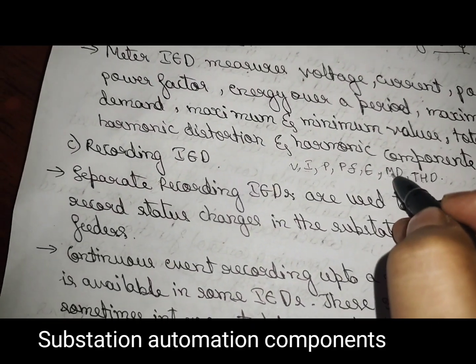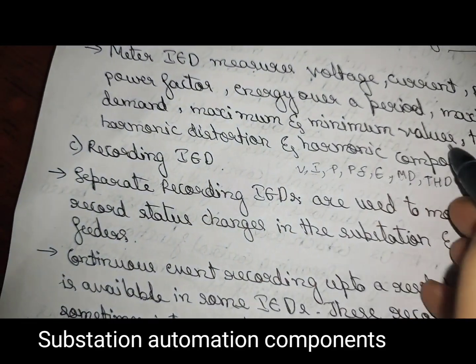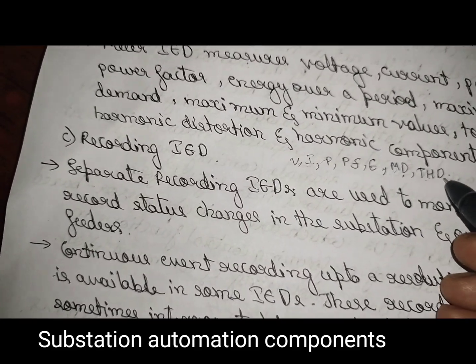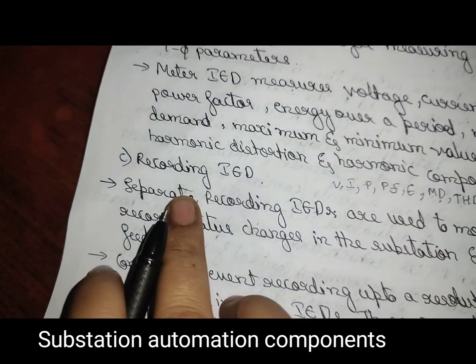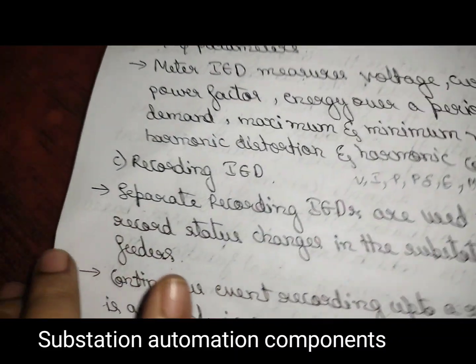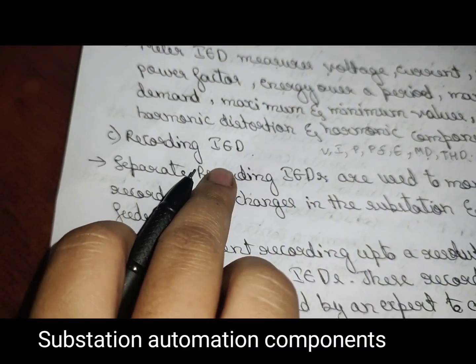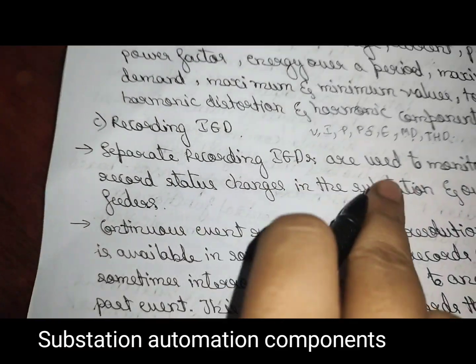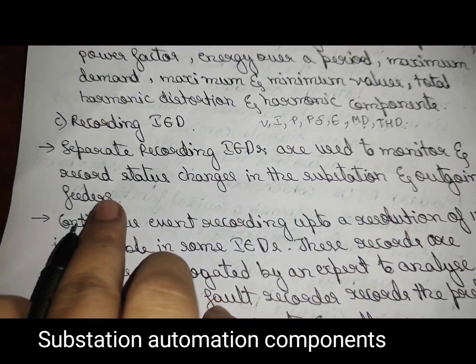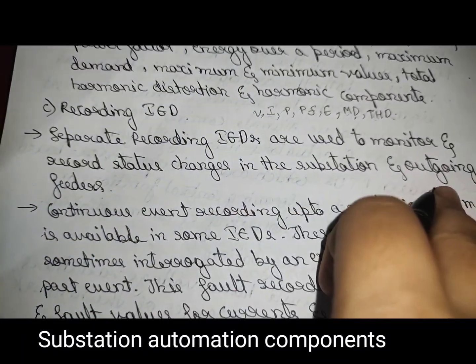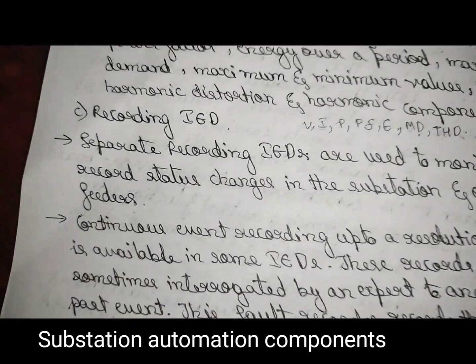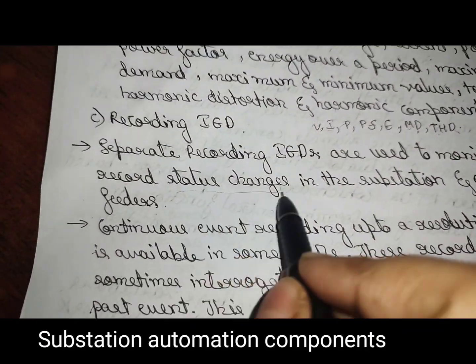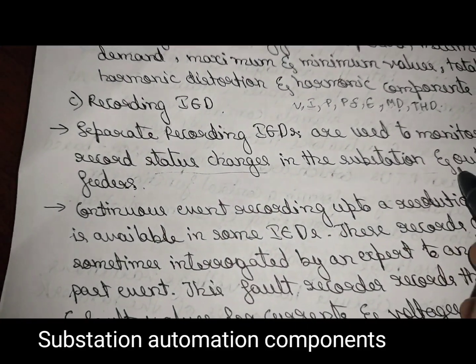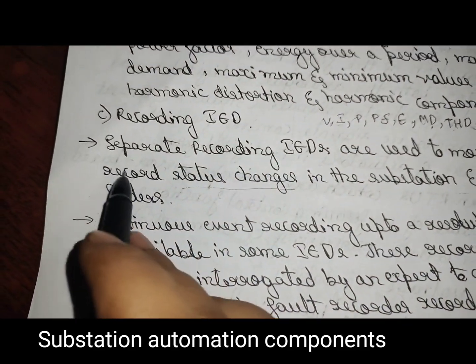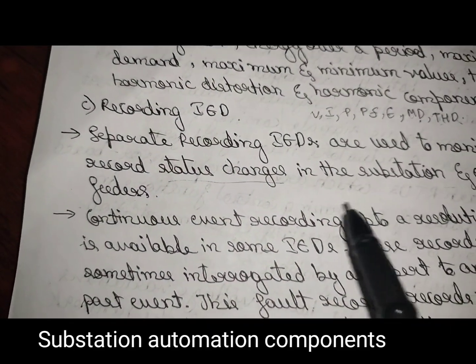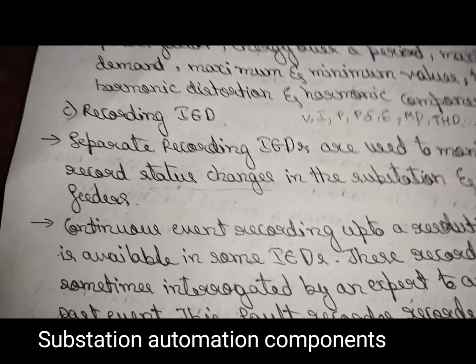So when it comes to the maximum, you can write maximum and minimum values also, total harmonic distortion and harmonic components. This is about the meter IED. Okay, recording IED, what will it do? Separate recording IEDs are used to monitor and record status changes in the substation and outgoing feeders. So if any changes occur in the substation and the outgoing feeders, it will record. It will be continuously monitoring. If any change occurs, then it will record.